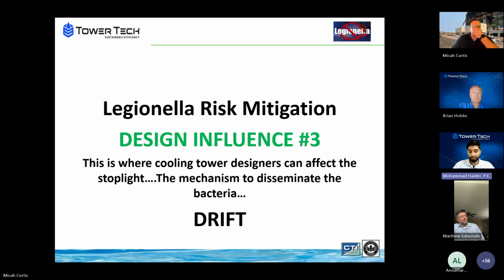Drift is actually the droplets of water that are carried out by a high velocity airflow. So airflow in the opposite direction to a tower is what creates drift, which is actual droplets of water. What you have on all towers are drift eliminators, which essentially force those droplets to start taking sharp turns with the hopes of catching those droplets and forcing them back into the system. But drift eliminators are not 100% effective. They do reduce a lot of drift, but typically they're not 100% effective.